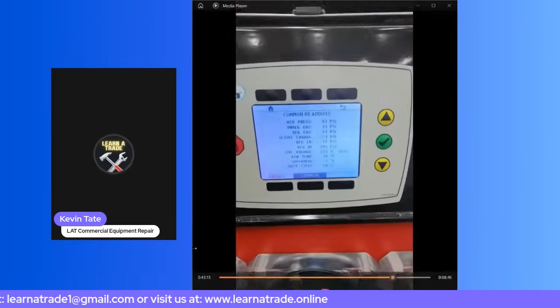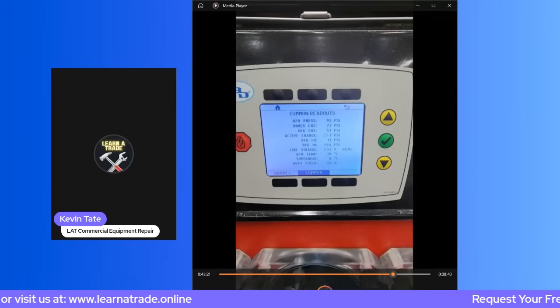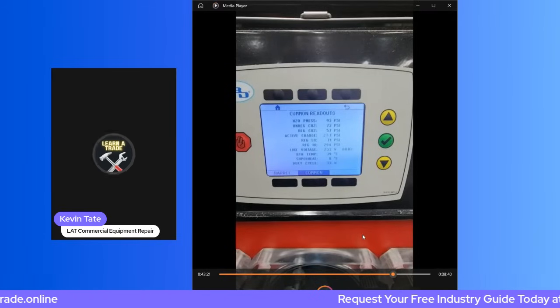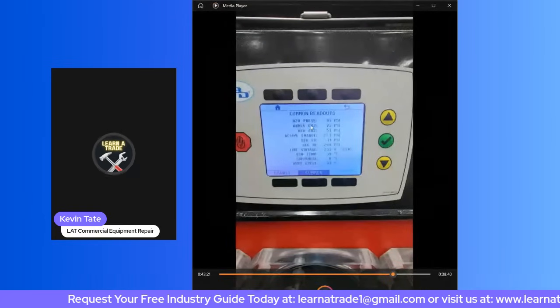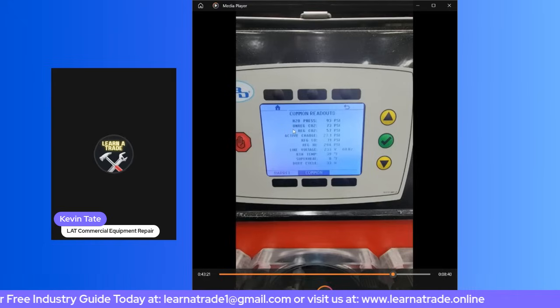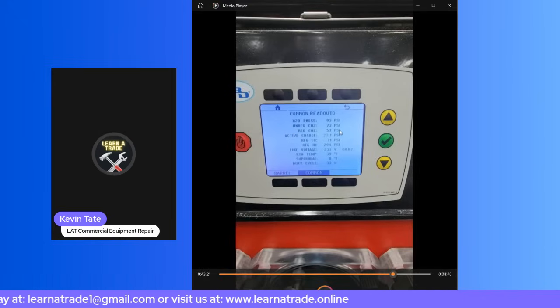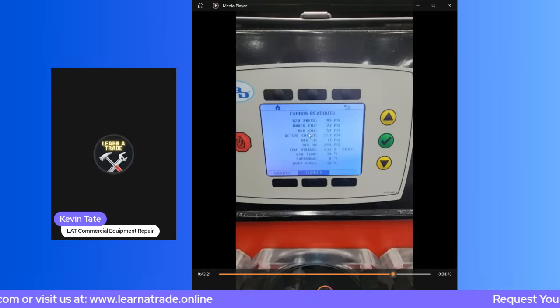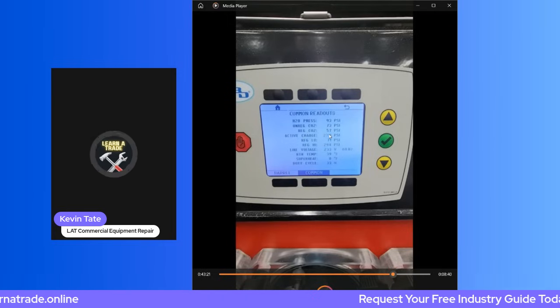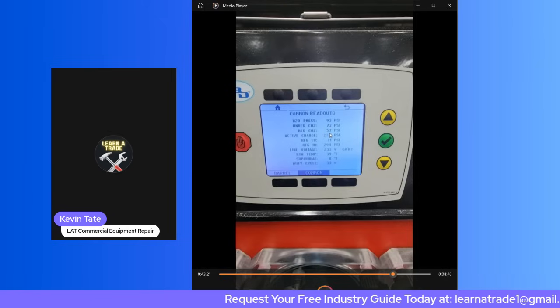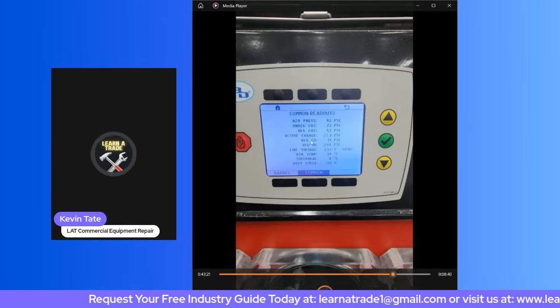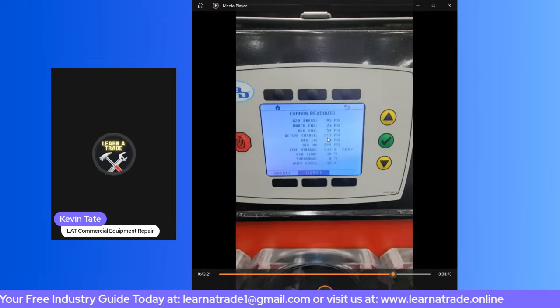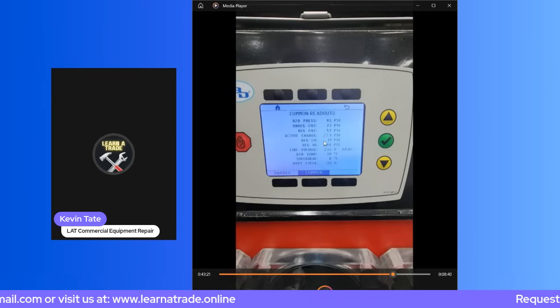I'm going to go to my readouts in the menu. Let's see if we can take a look here. So now I'm in my common readouts. This is basically showing you what the H2O pressure is, what your water pressure is, what your unregulated CO2 pressure is - that's at 73. Your regulated CO2 is at 57 right now. 60 is preferable, but it's within range. My active charge is at 27.1. The active charge usually gets up to 30 psi.